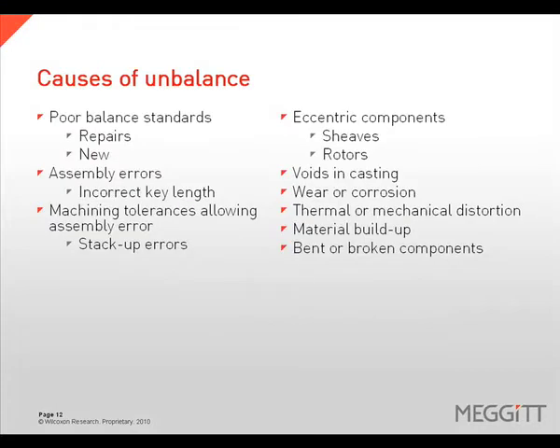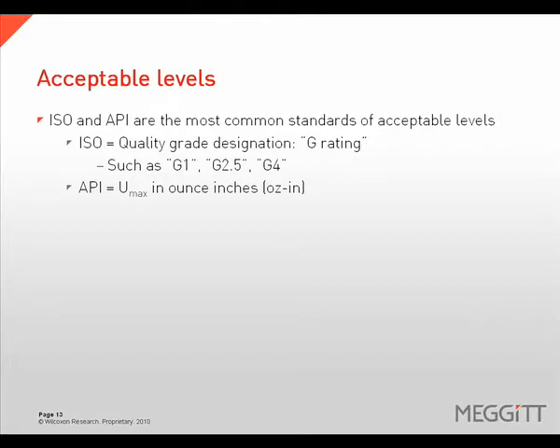There are many causes of unbalance, including poor balancing standards for repairs or new equipment, assembly errors such as the wrong shaft key length, machining tolerances stack-up error, eccentric components, wear or corrosion, and material buildup. To determine acceptable levels of unbalance, two standards are commonly used: the ISO and API standard. ISO assigns a G rating based on the amount of residual imbalance, while the API standard designates the remaining unbalance as UMAX expressed in ounce inches.